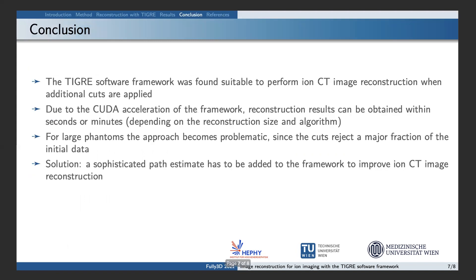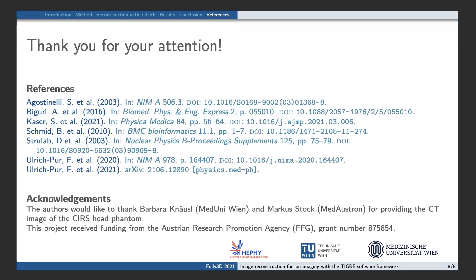To conclude, the TIGRE framework was successfully used for ion CT image reconstruction. Due to its CUDA acceleration, image reconstruction is possible within seconds to minutes, depending on the phantom size and reconstruction algorithm. The data cuts we used were able to improve the reconstruction results. However, the data rejection rate strongly increases with phantom thickness. In order to further improve ion CT image reconstruction with TIGRE, our goal is to implement a sophisticated path estimate to the framework. Thank you for your attention.